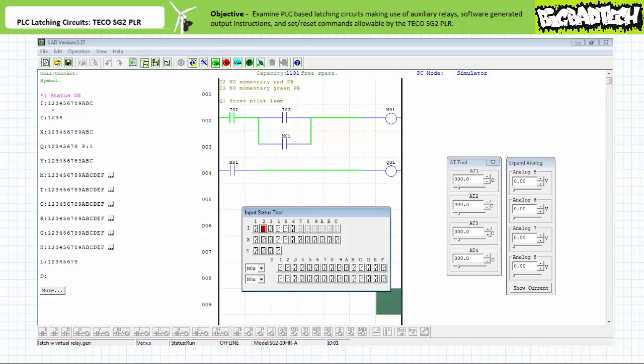The make instructions examining auxiliary relay M1 in both rungs 2 and 3 do not permit logical continuity, and output Q1 remains de-energized. When the simulated field input device on input 3 is closed, the make instruction examining I3 permits logical continuity onto auxiliary relay M1. The coil of auxiliary relay M1 is energized, and the make instructions examining M1 in both rungs 2 and 3 simultaneously establish a holding circuit and energize output Q1. When input 3 reopens, the make instruction examining I3 no longer permits continuity; however, the make instruction examining M1 still permits continuity onto the coil of M1, which remains energized, and output Q1 remains energized. The auxiliary relay has thus allowed the system to maintain the last asserted state.